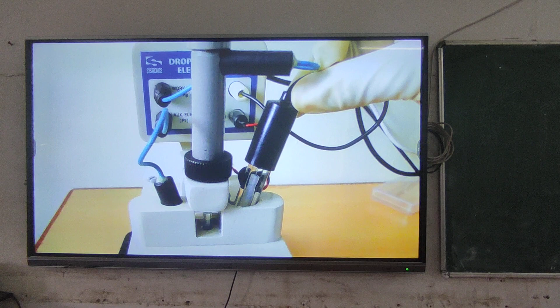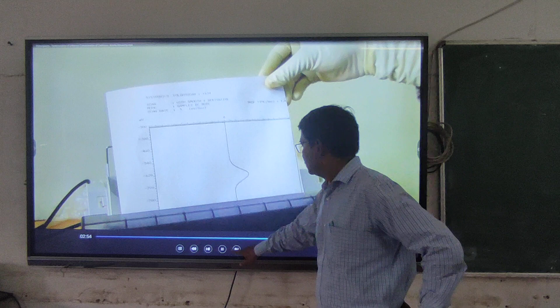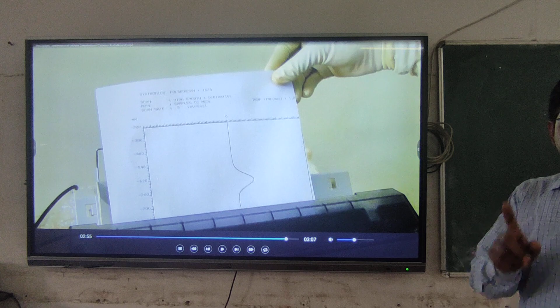First enter the initial millivolt and final scan millivolt and select the scan rate. Then choose the mode selection that you want, that is DC or sampled AC. If offset is present, remove the offset current by pressing yes. After scanning, choose the print option to generate the corresponding results. From the printed results, we get the half-wave potential and average limiting diffusion current of cadmium and zinc. So this gives the amount of metal ion present in the sample solution.